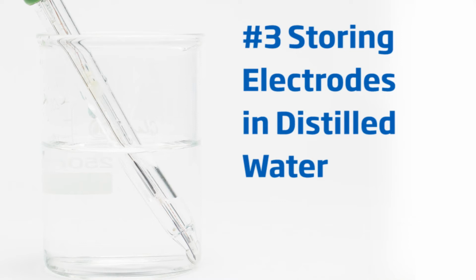We've come this far, and now it's time for our top 3 pH mistakes. Number 3 on our list is a common mistake, storing your electrode in distilled water. It is best practice to rinse your electrode with distilled water before using your cleaning solution and storing it in storage solution. But if you leave the electrode in pure water for too long, it will dilute the reference electrolyte. Diluted electrolyte causes inaccurate readings. So, like we've already said, when storing your electrode, be sure to use electrode storage solution. This will keep your electrode conditioned and working properly for much longer.